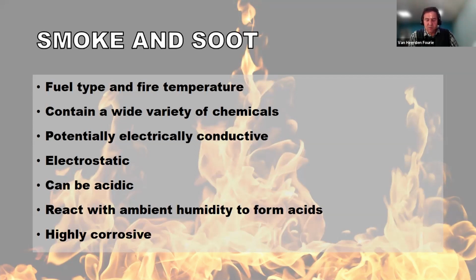Soot contamination on PC boards can have a delayed effect, especially where it reacts with moisture in the air at a later stage to form hydrochloric acid, or other corrosive acids, on the printed circuit boards. These acids then damage the conductive tracks on the printed circuit boards, which leads to premature failure of the electronic equipment. Soot contamination can be very corrosive and can affect all building materials and various aspects in the building. The soot particles are also electrostatic in nature and are attracted to other electrostatic surfaces, which creates a problem on medical equipment as well.